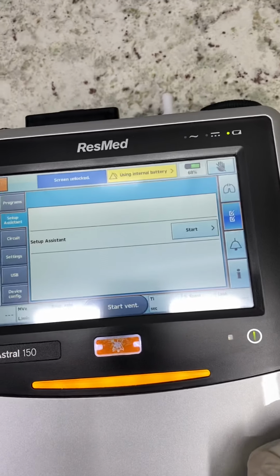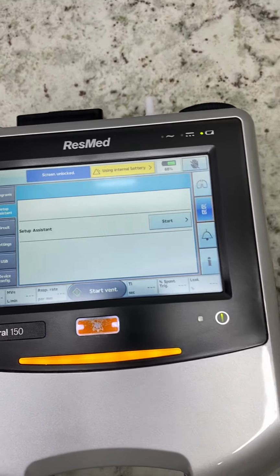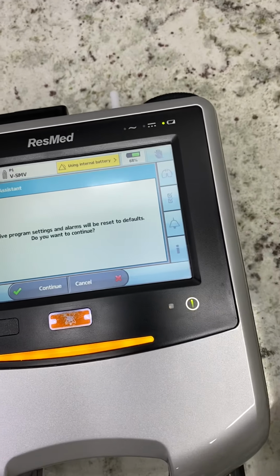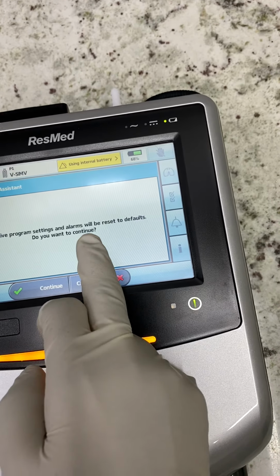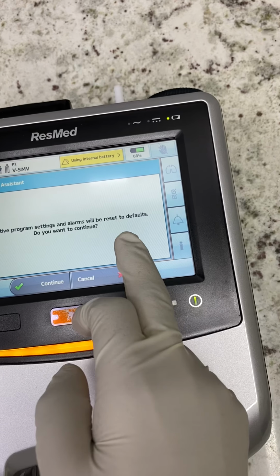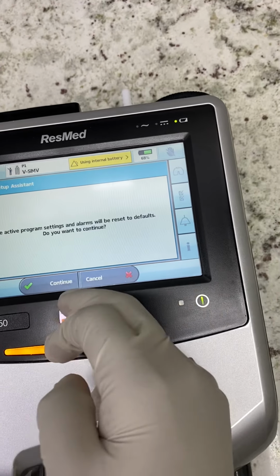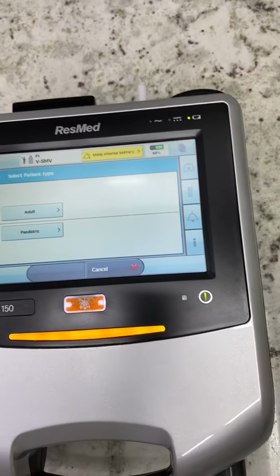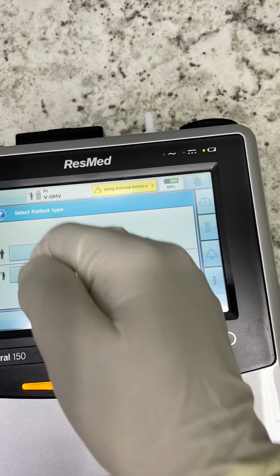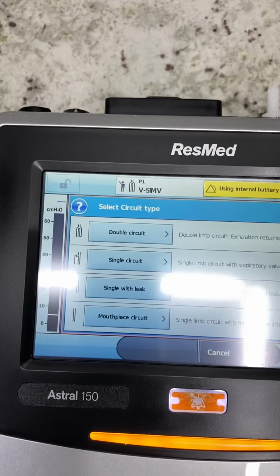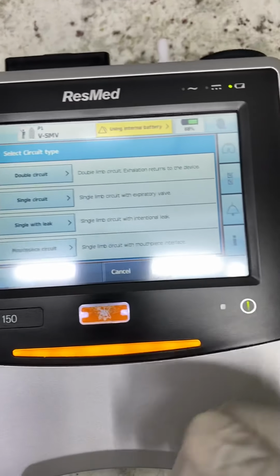Okay. So in setup assistant, it will tell you how to set up the ventilator. So it's all setup assistant. Start. The active program setting and alarms will be reset to defaults. Do you want to continue? Yeah, you can continue that. Continue. Then you can choose the patient group, adult or pediatric. So you choose the adult if you're using adult. Then these are the choices you have.